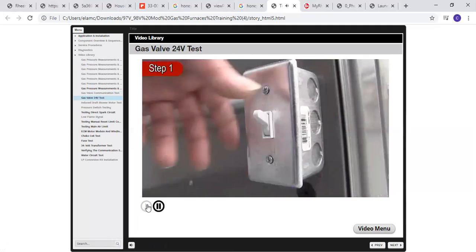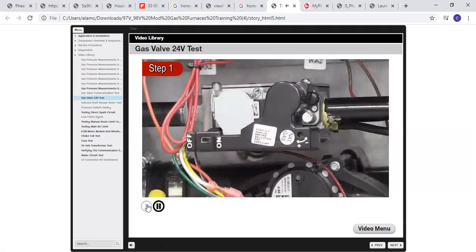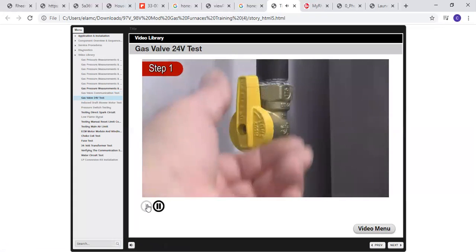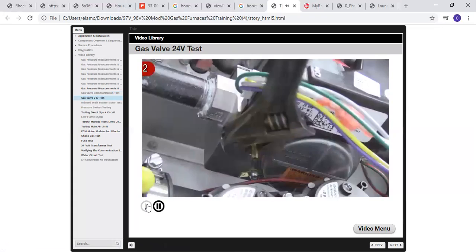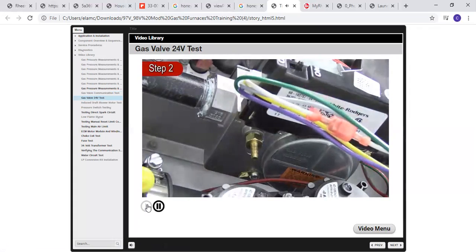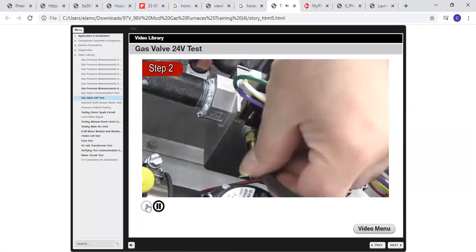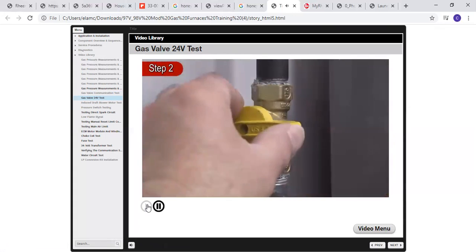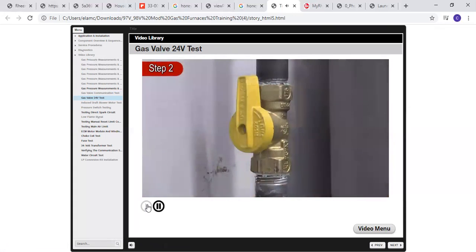Gas valve 24 volt test. Step 1. Shut off power to the furnace and ensure the gas valve on-off switch is in the on position. Shut off the gas supply to the furnace. Step 2. Install a gas manometer onto the inlet pressure port plug on the gas valve and turn on the gas supply to the furnace.